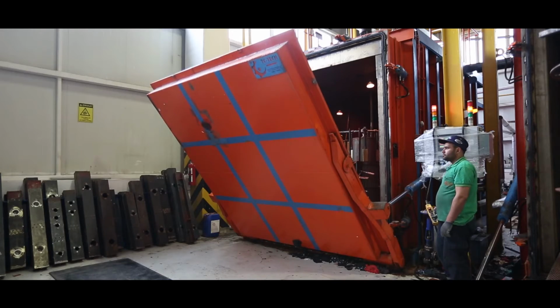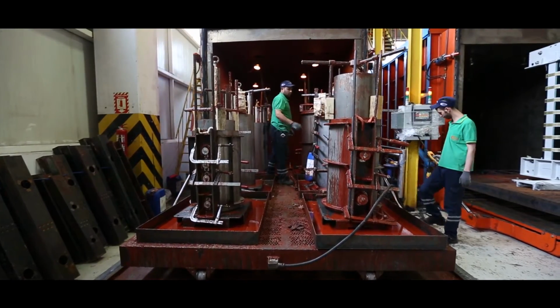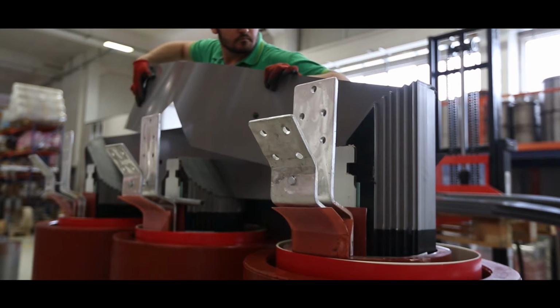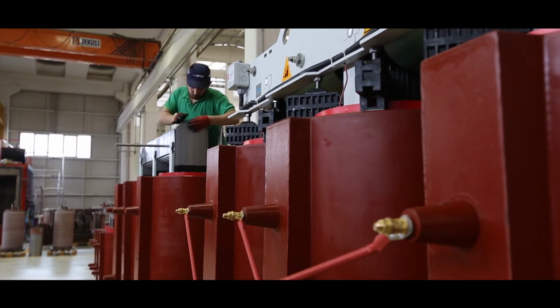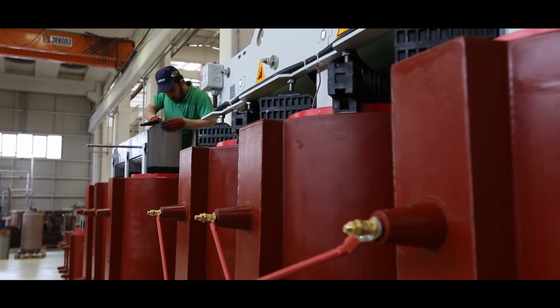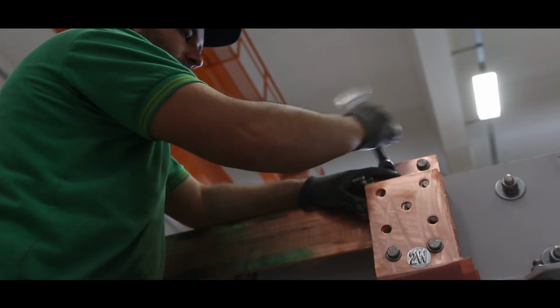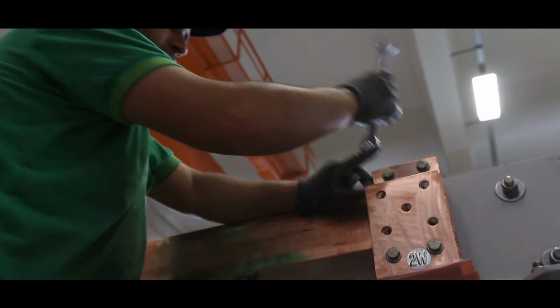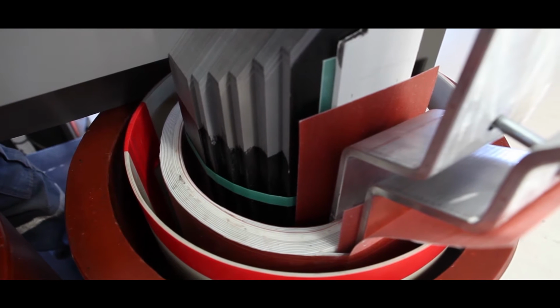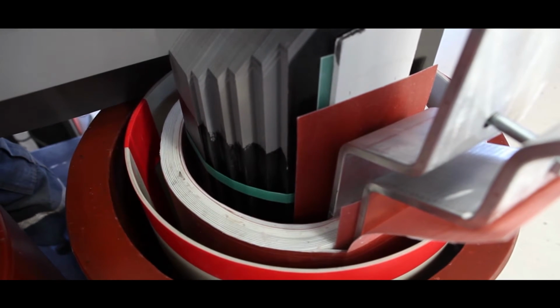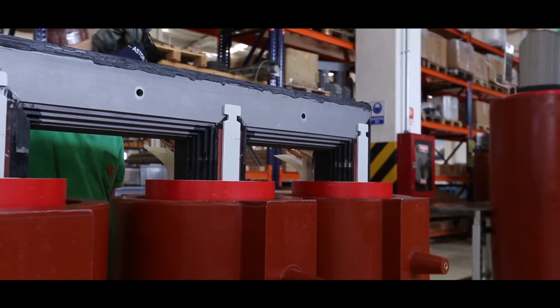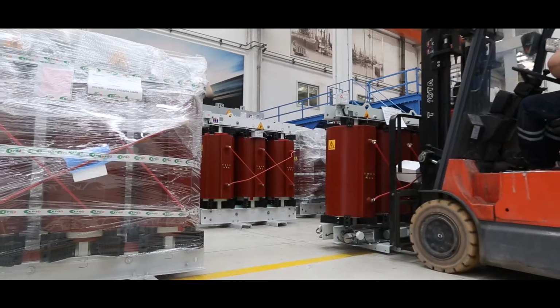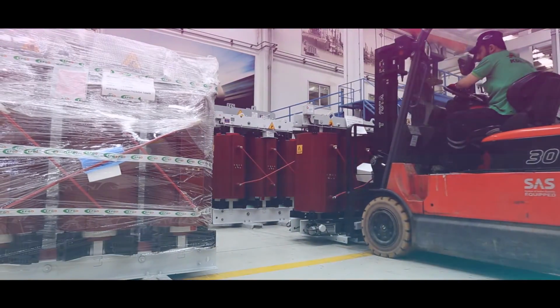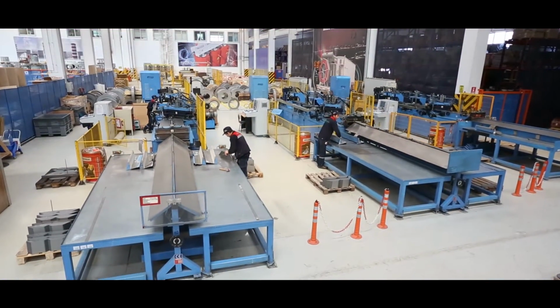Bobbins are provided resistance against difficult conditions and excellent dielectric features by being subjected to a hardening process following the winding process. High voltage bobbins are manufactured by use of copper and aluminium flat or round conductors with F or H class isolation depending on the project. Fine natural cooling is ensured within our designs by means of the effective dispersed cooling channels. Also, advantage is provided against high voltage surges.